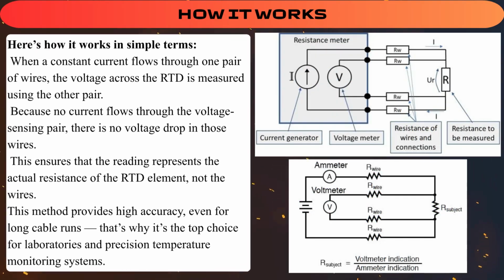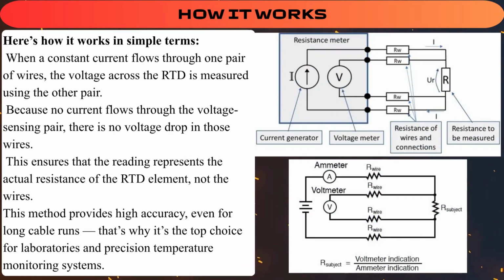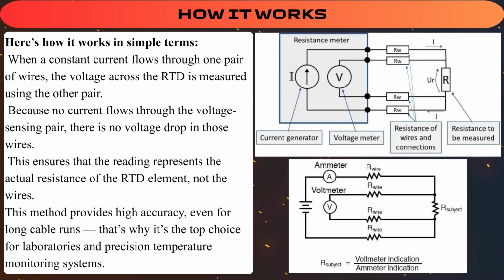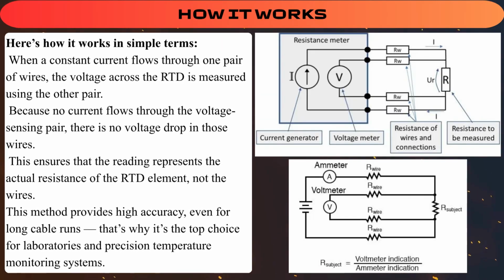How it works? Here's how it works in simple terms. When a constant current flows through one pair of wires, the voltage across the RTD is measured using the other pair. Because no current flows through the voltage sensing pair, there is no voltage drop in those wires. This ensures that the reading represents the actual resistance of the RTD element, not the wires. This method provides high accuracy, even for long cable runs. That's why it's the top choice for laboratories and precision temperature monitoring systems.